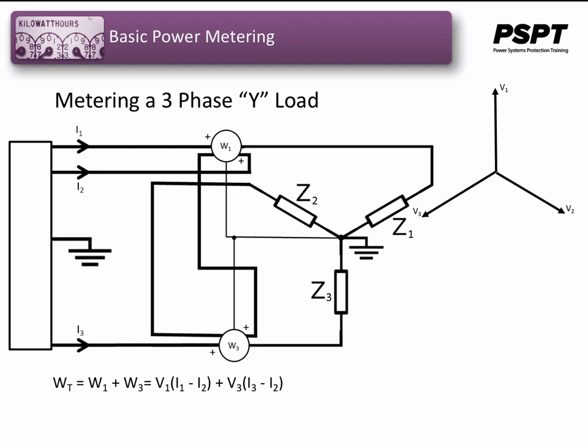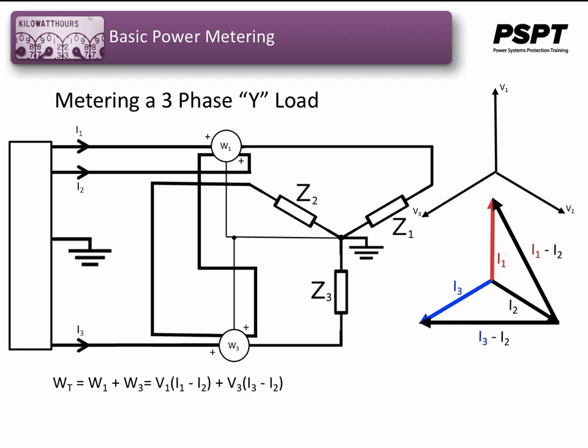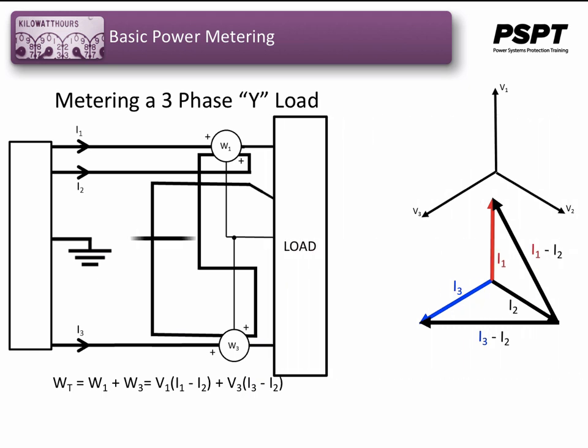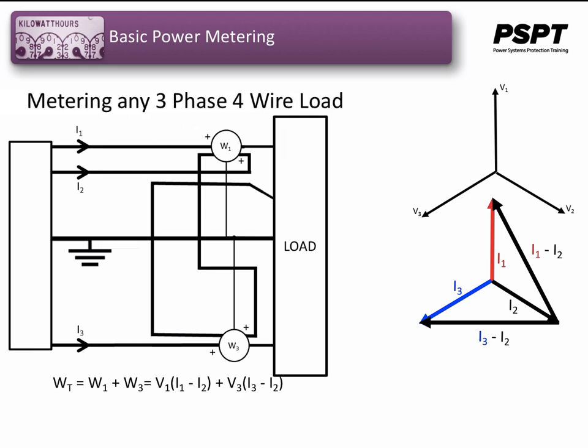Let's look at our 3-phase 4-wire load again, and let's apply just a purely resistive load. This is just to make things look a little bit simpler. The I1 current phasor would look like this. The I2 phasor would lag I1 by 120 degrees and look like this. I3 current vector would lag I2 by 120 degrees and look like this. The I1 minus I2 current phasor would look like this. And the I3 minus I2 current phasor would look like this. In actual fact, the load does not have to be a Y configuration, since the calculations only deal with current and voltages to the load. This metering will work for any 3-phase 4-wire load.